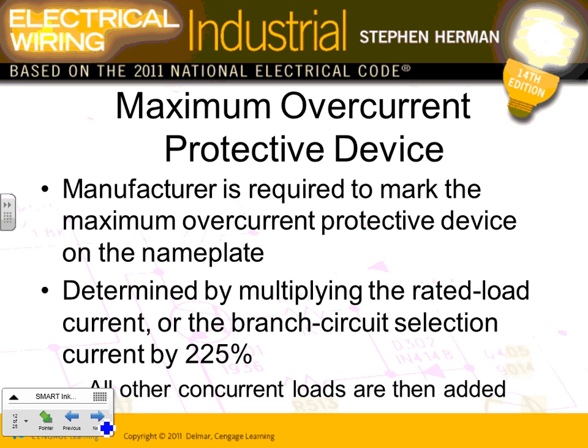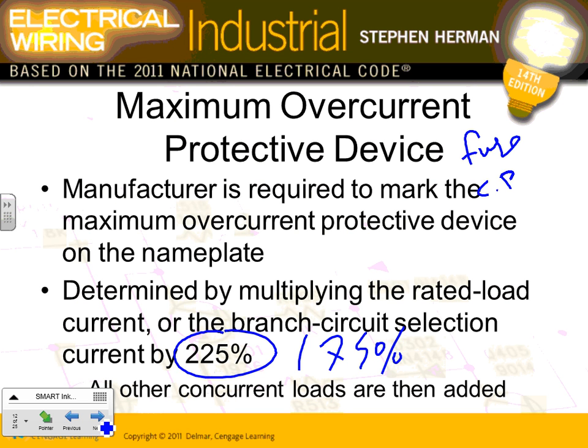Maximum overcurrent device. Remember the code says 225% or 175%, and we use 175% if we don't know because we're conservative. The manufacturer can use either 225 or 175 to size the overcurrent device. We don't care which one they use, as long as they put it on the nameplate of their equipment, because they know their equipment and we're protecting their equipment. That's the fuse or circuit breaker size. How do they do it? They take this number multiplied by rated load amps or branch circuit selection current, whichever is larger.